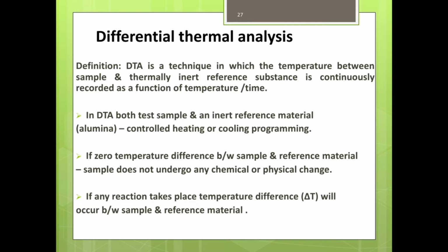In DTA, both the test sample and the inert reference material, alumina, undergo controllable, programmable heating and cooling. If the difference between the sample and the reference material is zero, they do not undergo any chemical or physical change.